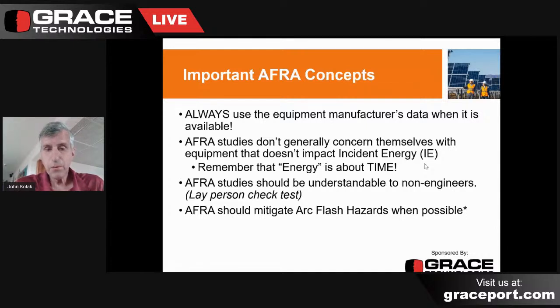It would also be, we'll talk later about using SCADA, supervisory control and data acquisition, to get actual numbers that are, especially on solar farms, oftentimes the system operates at a different value, voltage, for example, than it does on the nameplate. So always use real data if you can, as opposed to calculated data.